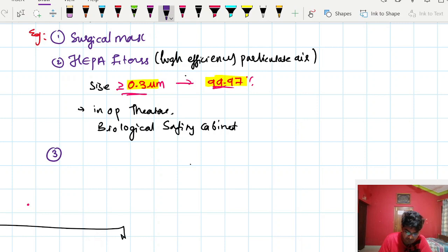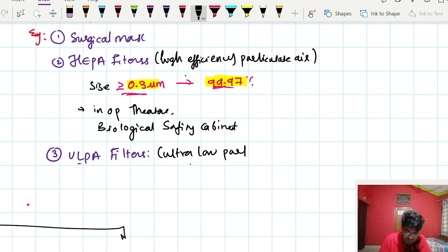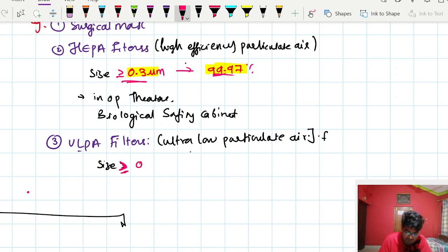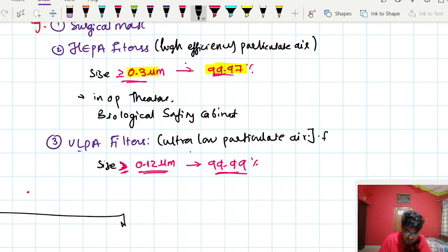The next important surface filter is ULPA filters — Ultra Low Particulate Air filters. ULPA filters are more efficient than HEPA filters because their pore size filters substances of size greater than or equal to 0.12 micrometers, with an efficiency of 99.99%. So ULPA filters are more efficient than HEPA filters.